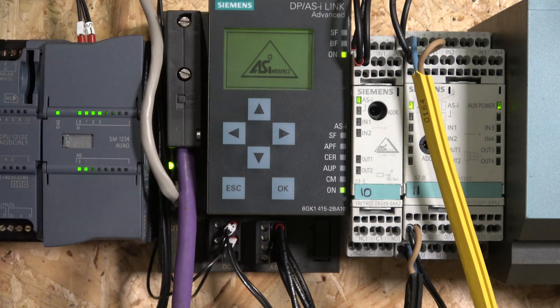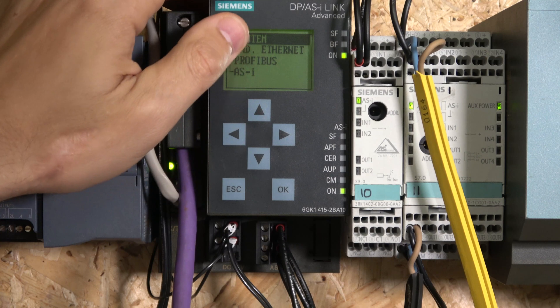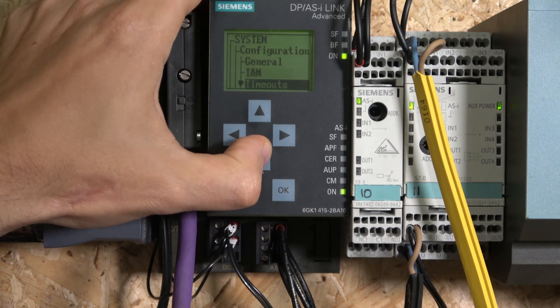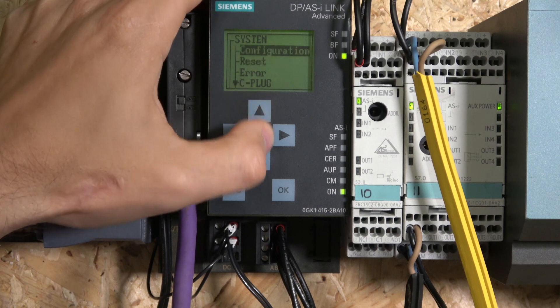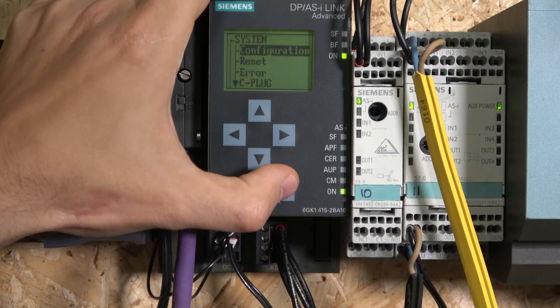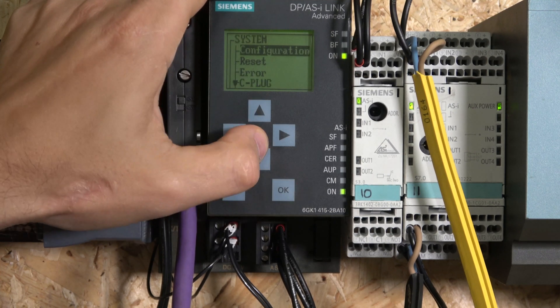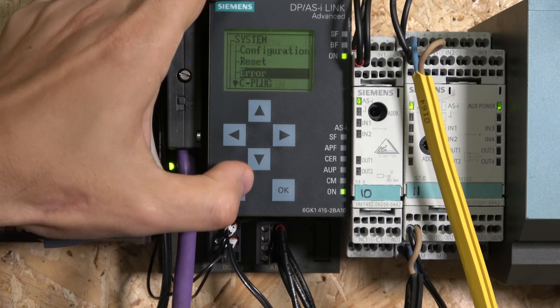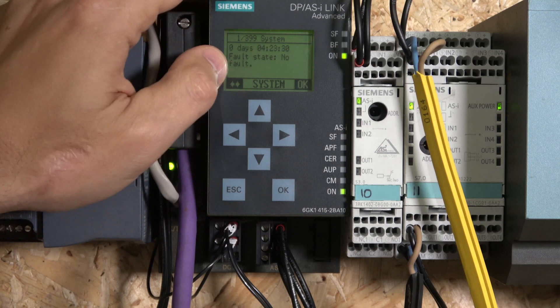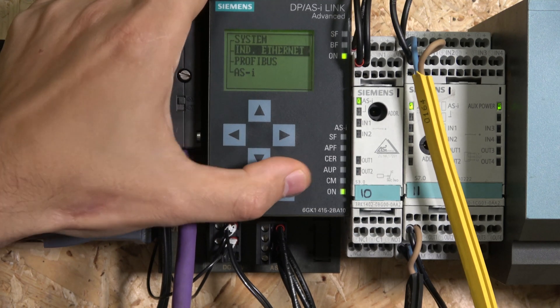I'll put the Profibus cable back in - you can see the errors disappear. Going through the LCD display: clicking OK gives you System, IND ETHERNET, Profibus, and ASI. In the System menu, there are basic settings like language, timeouts, and general configuration. You can reset in here. Then there's a C plug section where you can transfer data, and diagnostics showing buffer fault state.